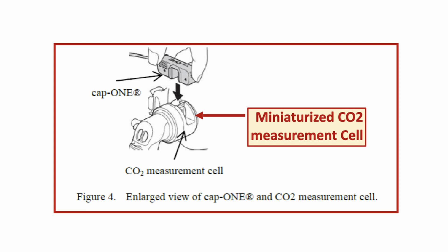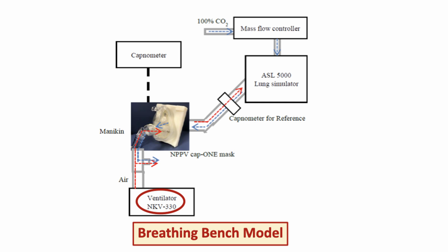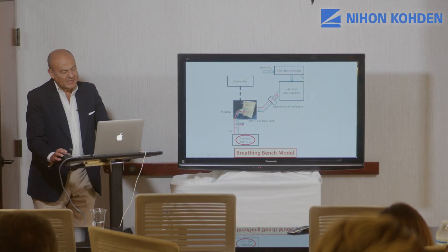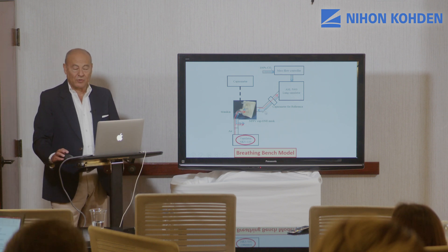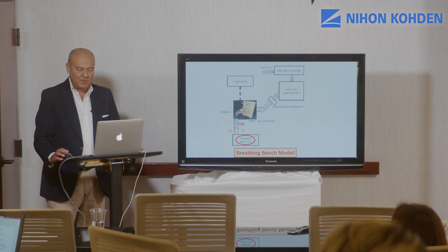Here you can see another enlarged view of the cap-ONE CO2 measurement cell. It is extremely light, and importantly, the CO2 measurement cell is embedded in the mask, so all problems related to the positioning of the measurement cell are apparently solved. The breathing bench model designed for this pilot bench study was made using a head mannequin provided with mouth and nostrils, fitted with the NPPV cap-ONE mask, ventilated by an NKV-330 ventilator, driven by an ASL 5000 active lung simulator that received a continuous measured flow of CO2 through a mass flow controller. The system contained two capnometers: one reference capnometer positioned between the ASL 5000 lung simulator and the mannequin, and the other connected to the NPPV cap-ONE mask.